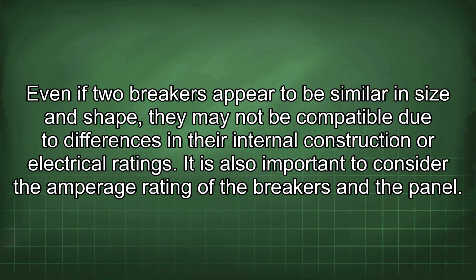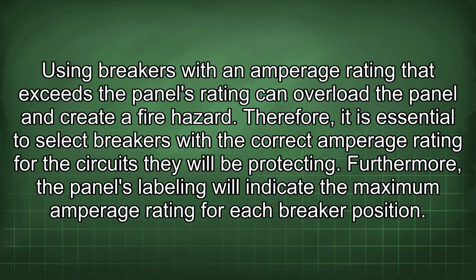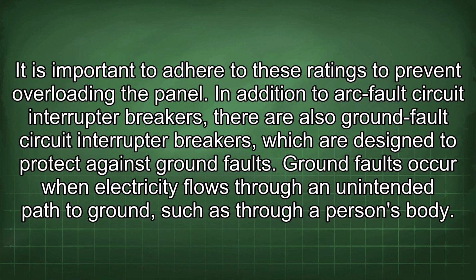It is also important to consider the amperage rating of the breakers and the panel. Using breakers with an amperage rating that exceeds the panel's rating can overload the panel and create a fire hazard. Therefore, it is essential to select breakers with the correct amperage rating for the circuits they will be protecting. Furthermore, the panel's labeling will indicate the maximum amperage rating for each breaker position. It is important to adhere to these ratings to prevent overloading the panel.